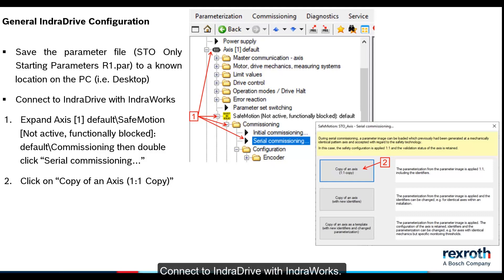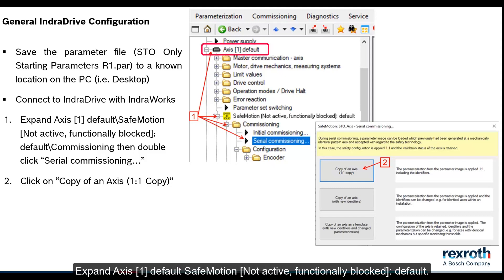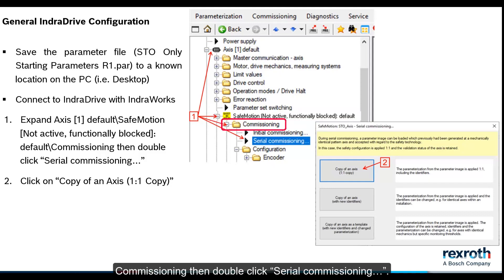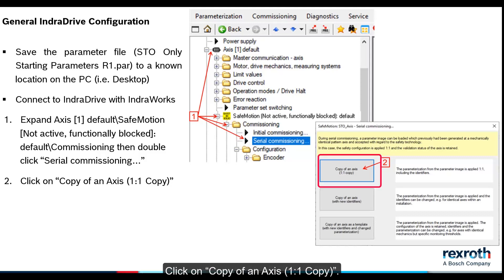Connect to IndraDrive with IndraWorks. Expand axis 1 default. SafeMotion not active, functionally blocked, default, commissioning. Then double-click serial commissioning. Click on copy of an axis, 1 to 1 copy.